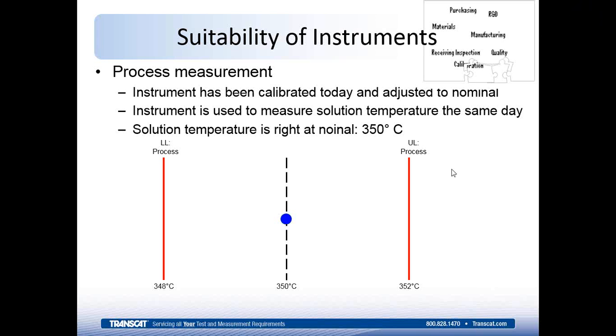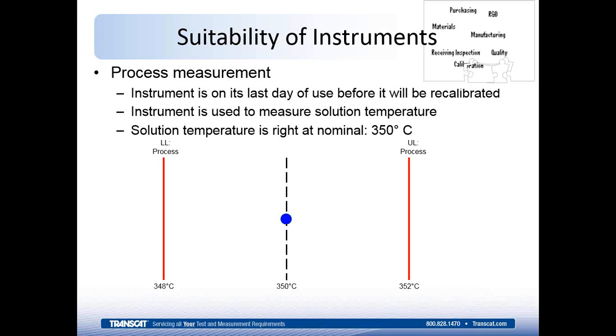Usually they're on a 1-year interval or perhaps some other interval, but the majority of what we see from our clients is a 1-year interval. So what if it's on its last day of use before it's going to be recalibrated? Again, using a 1-year interval as an example, today is the 364th day. It's going to be calibrated today or tomorrow. And where is that instrument today, that temperature instrument I'm using to measure the solution? Has it drifted? How's it been handled? How's it been stored over time? So I don't know where that is until it gets sent in for calibration again.